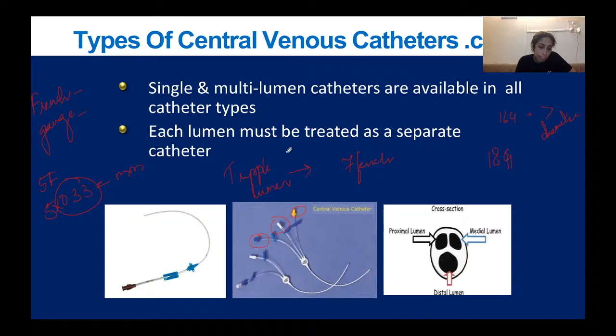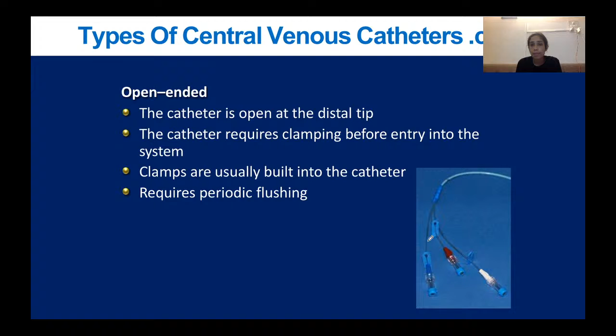So this multi-lumen catheter is basically a triple lumen, which is a 7 French catheter, and it has an outside diameter of 2.3 mm, and that is 7 French, and it houses one 16 gauge and two 18 gauge channels. Now open-ended, the catheter is open at the distal tip, and the catheter requires clamping before entry into the system. Clamps are usually built into the catheter and require periodic flushing. So these blue things here are the clamps that are built into the catheter, and this is from where the flush has to be given.